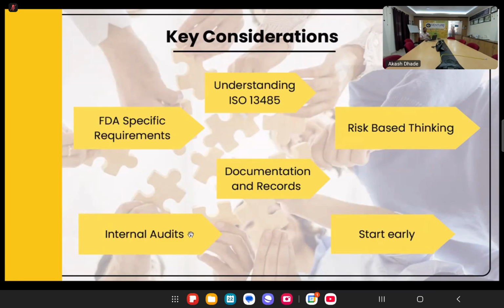Then internal audits. This is the gate before you go for any FDA clearance or FDA approval. Your internal audit should be robust enough to identify key areas and also find out improvement areas for QMSR compliance. So you should have internal auditors who are very well versed with ISO 13485 as well as QMSR. They will identify these areas and suggest the remedial actions. Once you do that, then you are pretty sure that you are in alignment with QMSR. Then you go for FDA approval or clearance.